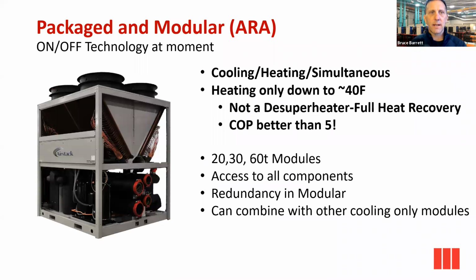All right, on to a different technology, some packaged equipment. We've got an air-cooled chiller that can make hot water. We're employing on-off compressors at the moment. There are no variable speed compressor options on the market for this machine. One big reason why is we have 3 heat exchangers. We've got an evaporator, we've got a condenser, both braze plate, and we have the coils. That's our 3rd heat exchanger. We do them in 20, 30, and 60-ton modules. They're modular, so you can put multiple machines together. You can pair these with just cooling-only machines. You don't need the entire array.